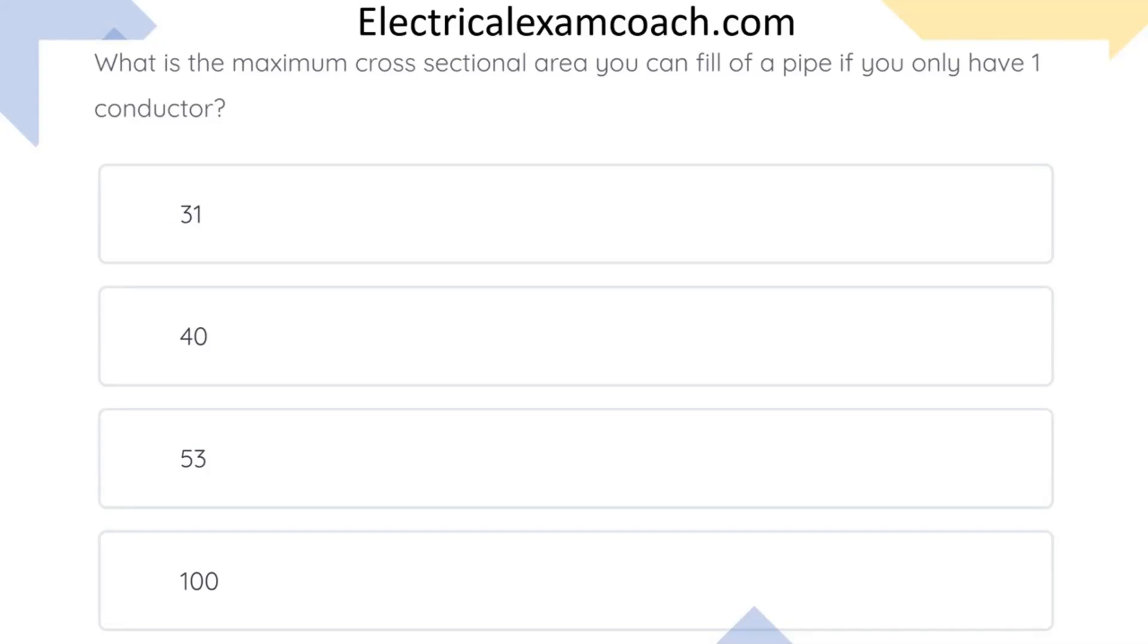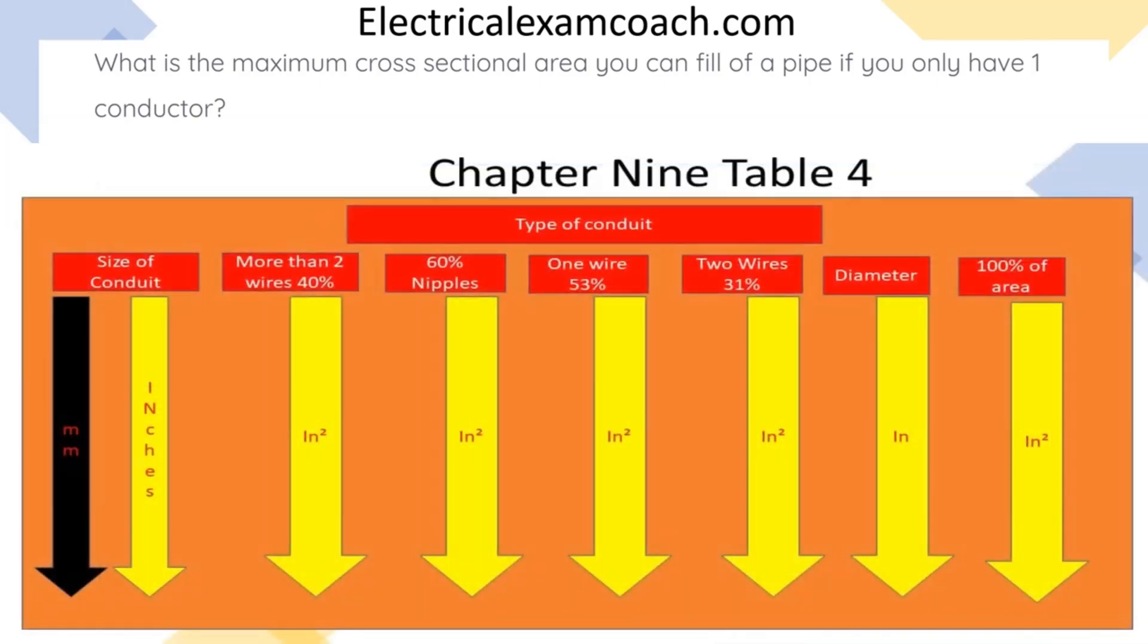What is the maximum cross-sectional area you can fill of a pipe if you only have one conductor? The correct answer is 53%. We're going to find this in the Chapter 9 Table 4 tables.